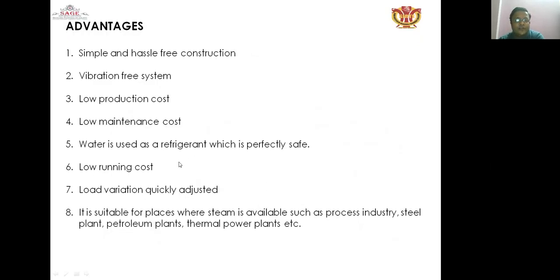What are the advantages of the steam jet cooling system? Simple and hassle-free construction, vibration-free system, low production cost, low maintenance cost. Water is used as a refrigerant. No other refrigerant is required. Low running cost. Load variation is quickly adjusted. If the fluctuating load increases, there will be no shutdown of the steam jet refrigeration system. It is suitable for places where steam is available, such as process industries, steel plants, petroleum plants, and thermal power plants.